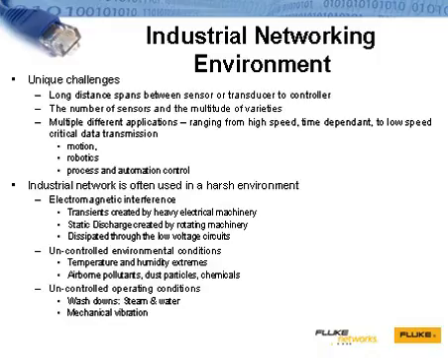on all the connections. We've also run into overlong cabling runs at a wastewater treatment plant in order to support applications at opposite ends of the plant. And excessive ringing introduced by a short cabling run between equipment installed in a control cabinet that created an impedance mismatch. So, unshielded twisted pair copper cabling can be damaged by both prolonged sunlight and freezing temps. The electromagnetic interference, or EMI, generated by electrical equipment causes noise that impedes network traffic. And corroded connections of any type create performance issues.